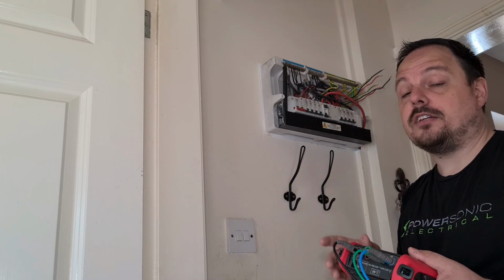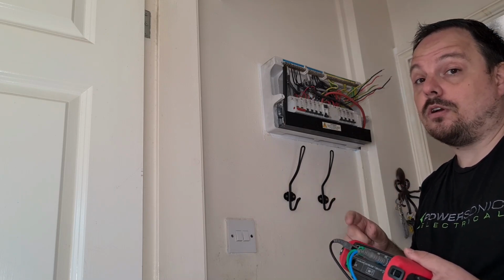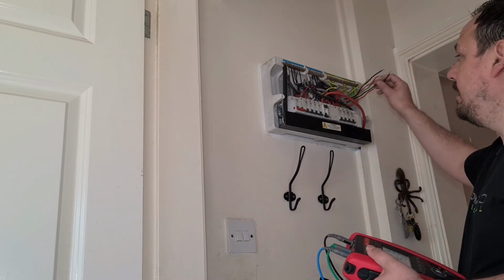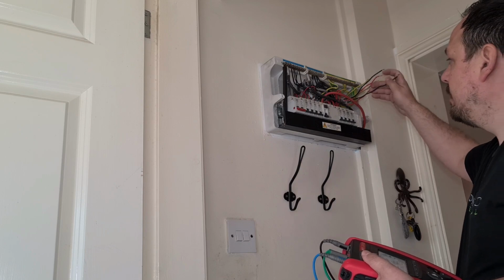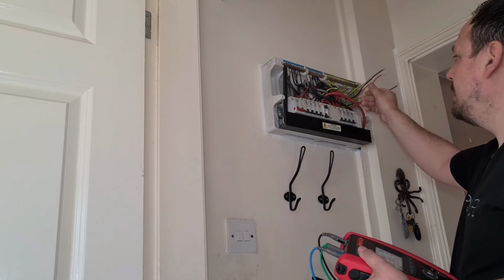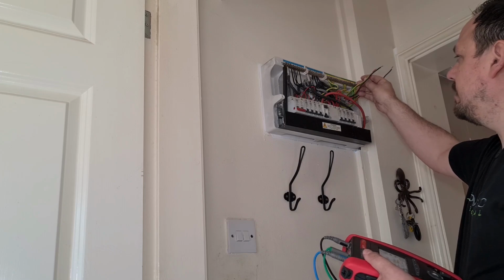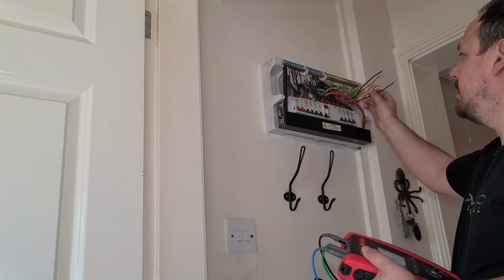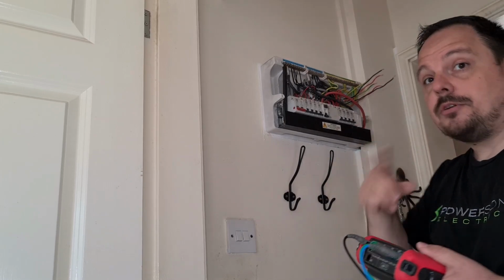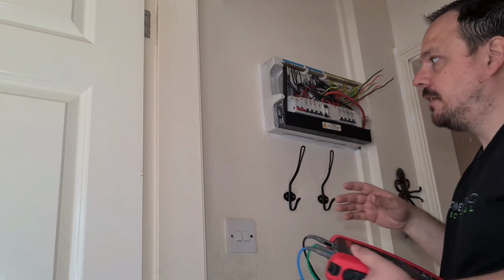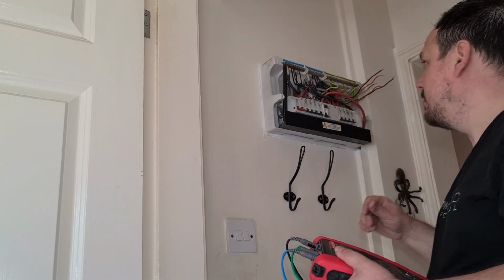Primarily the values should be roughly the same, and that would be your big R1 plus your big R2. You can also throw the neutral in there as well, so you can basically cross over your line and CPC on this leg with your line and CPC on the other leg, run around and get your R1, R2s - should be reasonably consistent aside from any spurs that might be in the circuit.